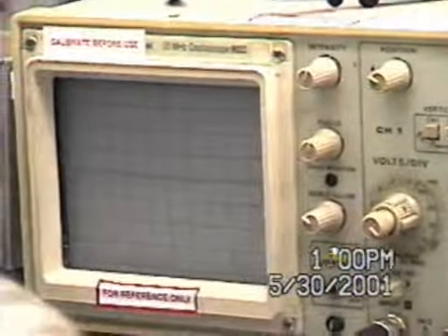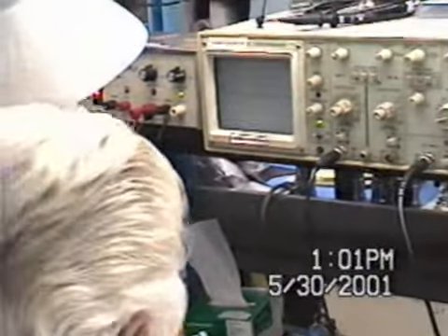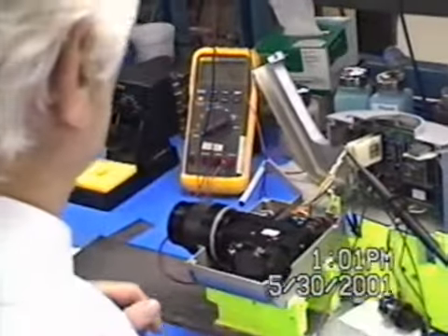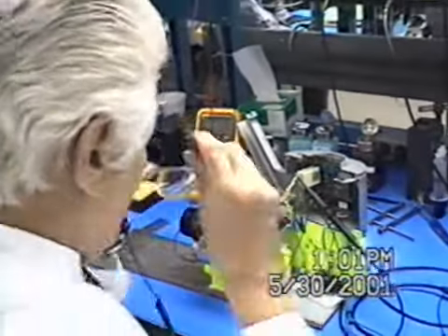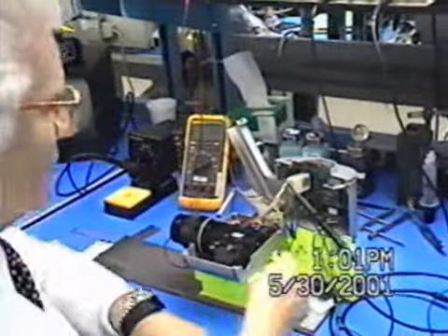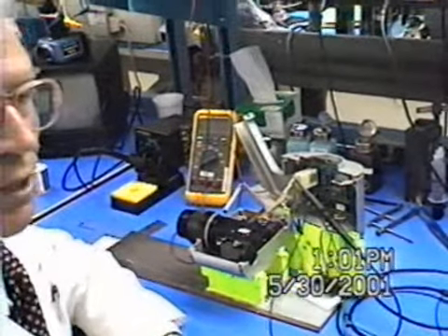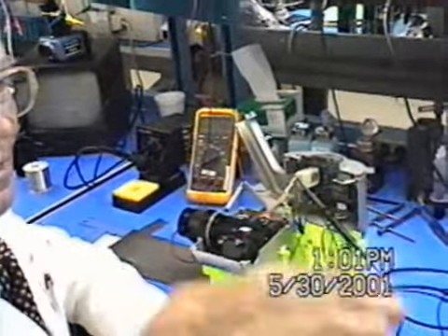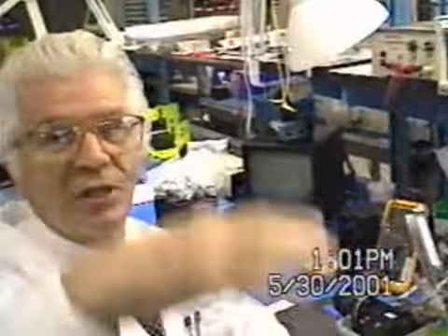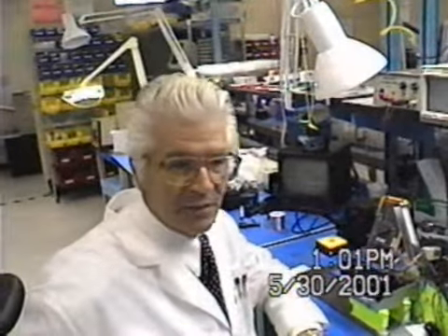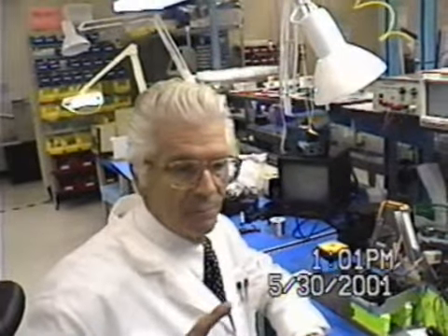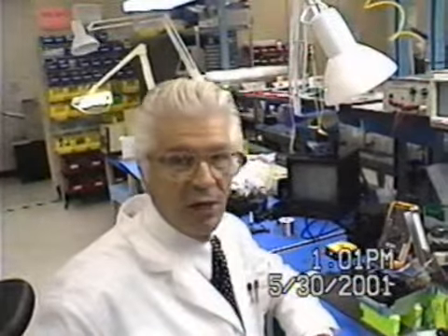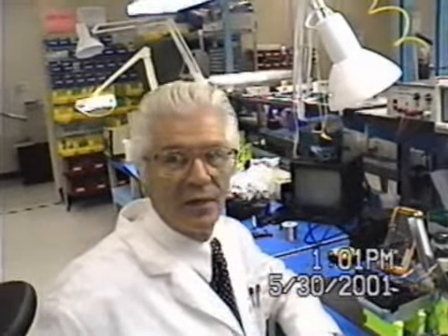That is, I would say the best thing is to change that resistor down there, and I'll tell you why. You can also increase it, I can adjust the emissivity by the span here, but what you're doing is you have a voltage divider, cut the signal too much down, and then you use an amplifier to bring it up. That's not very good practice. The best practice is to adjust the voltage divider correctly, so you're close to the right number.